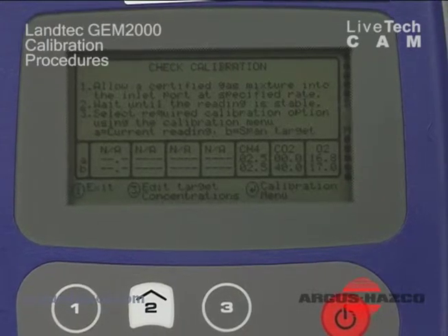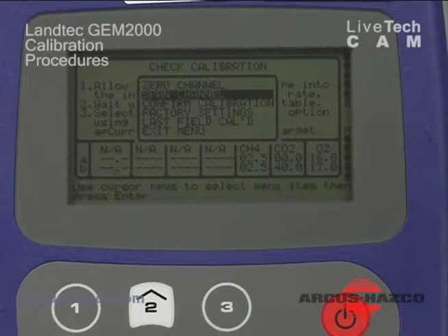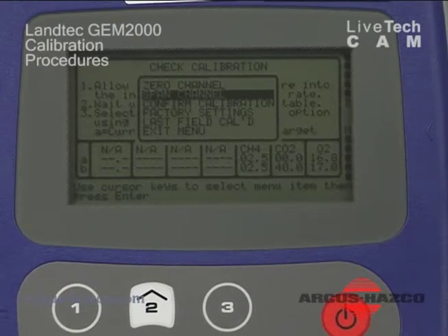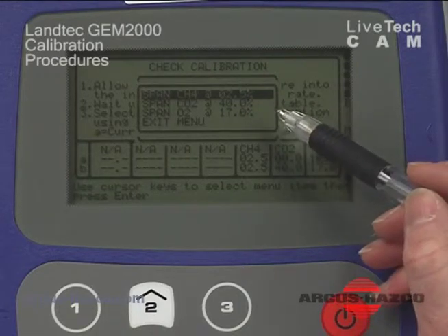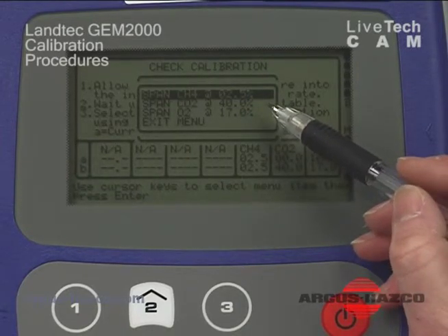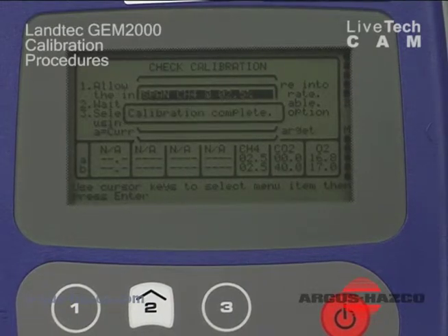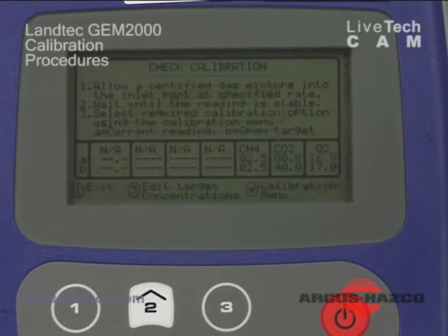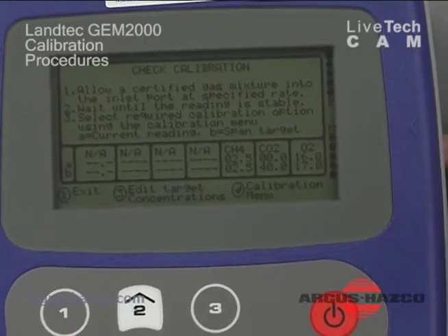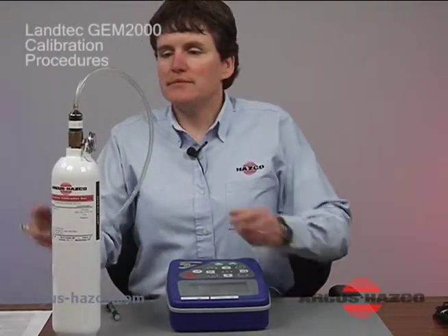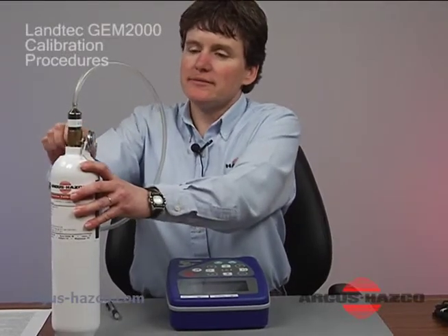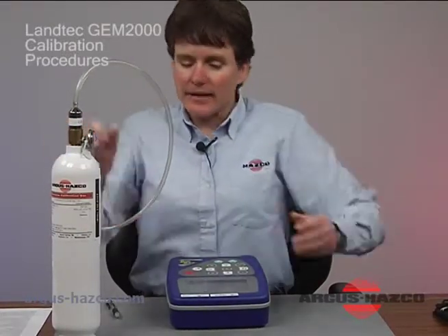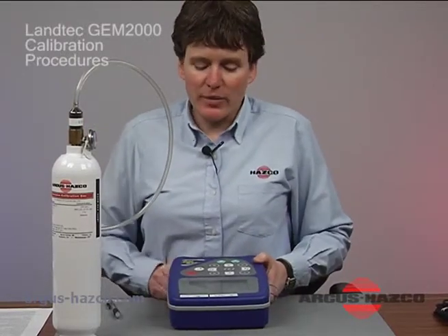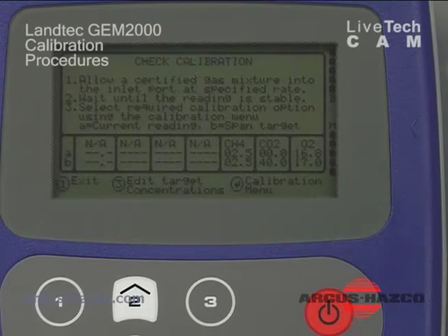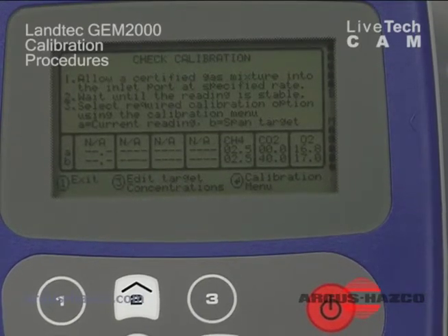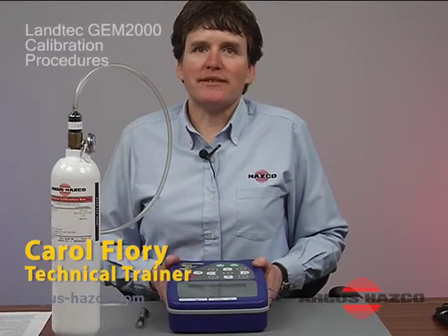calibrate. It's going to ask me to select. I need to arrow down to select my span. I hit Enter. And right now I want to span my CH4 to the 2.5% as I set it. I hit Enter. My calibration is complete. I go ahead and remove my inlet tubing, turn off my regulator, and then the calibration is complete for that parameter. And again, you would continue in this fashion for each sensor installed in the unit. And then that concludes the calibration portion of the GEM 2000.